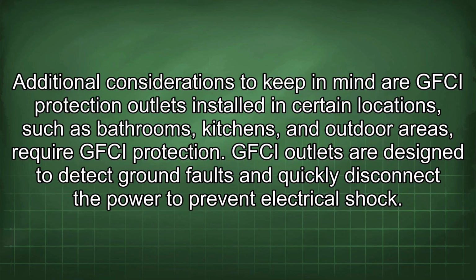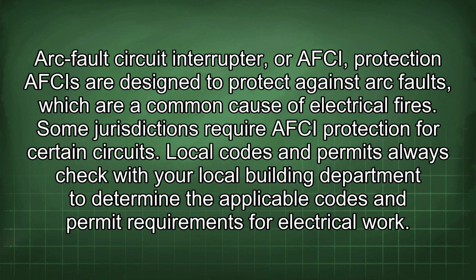Additional considerations to keep in mind. GFCI protection: outlets installed in certain locations, such as bathrooms, kitchens, and outdoor areas, require GFCI protection. GFCI outlets are designed to detect ground faults and quickly disconnect the power to prevent electrical shock. Arc fault circuit interrupter, or AFCI, protection: AFCIs are designed to protect against arc faults, which are a common cause of electrical fires. Some jurisdictions require AFCI protection for certain circuits.